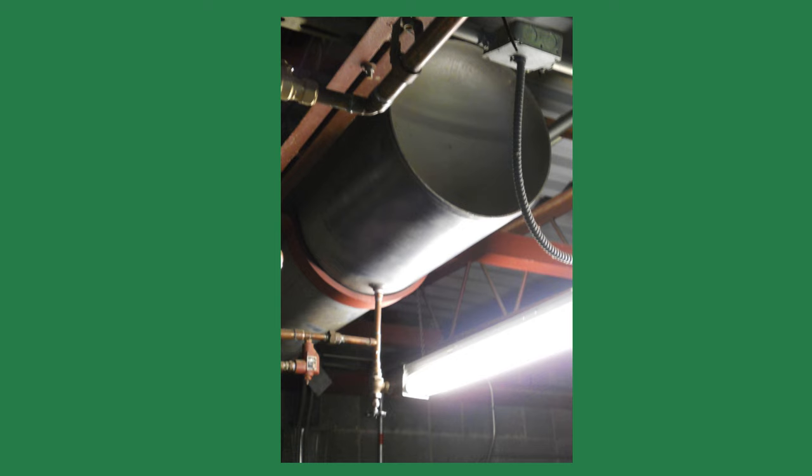The tank is too small. This will usually present itself from the start. I like asking the customer when the problems first started. If it's a relatively new problem, the tank is probably not undersized, unless conditions have changed.